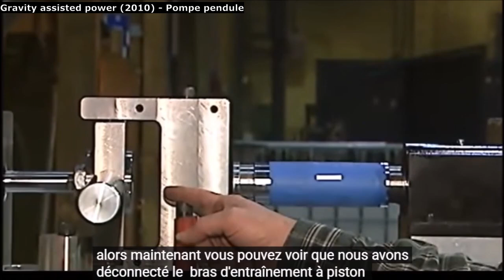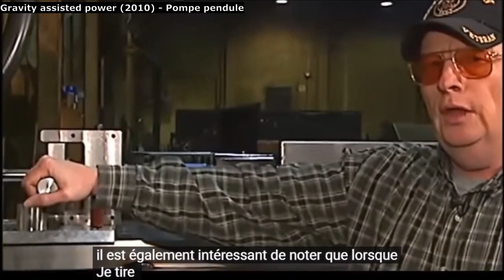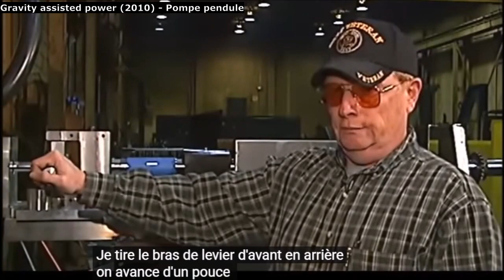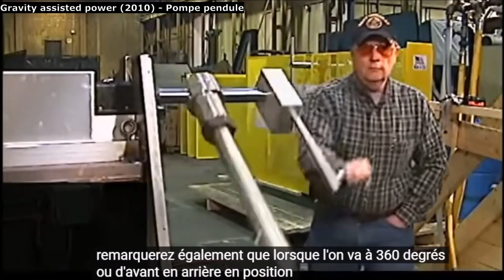Now we've disconnected the piston drive arm from the pendulum pump, and we have the pump set up strictly as a lever arm pump. The lever arm is 16 inches long, the same setting as on the pendulum pump. When I pull the lever arm back and forth, we're going 1 inch, the same distance as when going 360 degrees in a horizontal position with the pendulum pump.